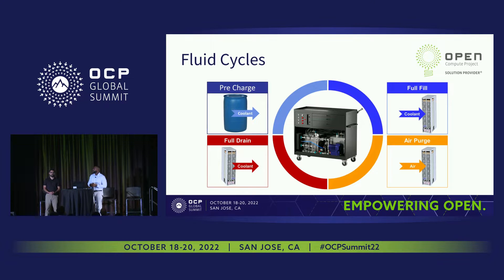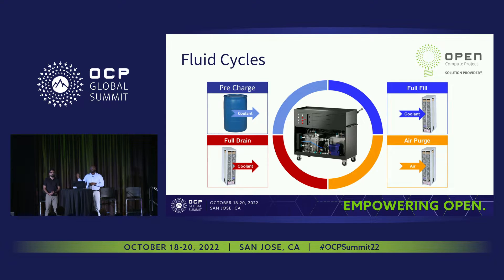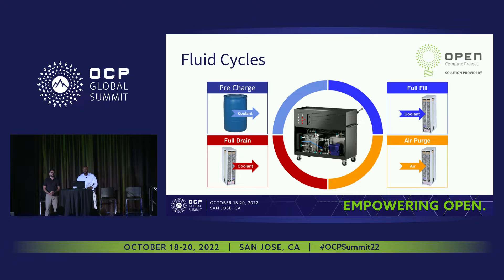There are four fluid cycles: pre-charge, fill, drain, and purge. For pre-charge, you connect the cart to a tank or tub of fluid and fill the new coolant reservoir before performing a service operation — this would be done at a stationary fill station. Then for full fill, you take that coolant pre-charged into the cart and install it into an AALC rack. The drain function is for servicing and would only be used if you needed to entirely drain a rack, though racks do not need to be fully drained to be transported. Finally, air purge ensures that all the fluid from a drained rack is removed.